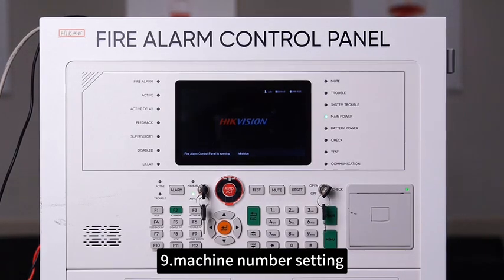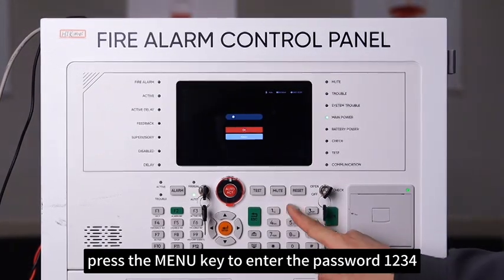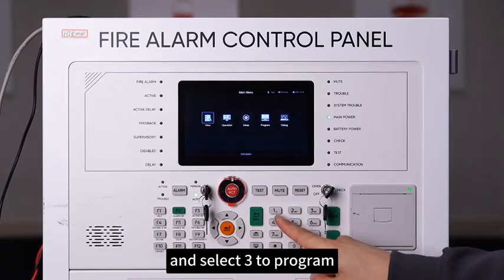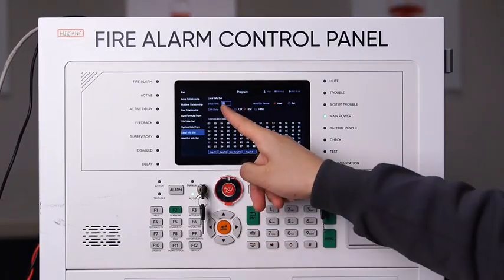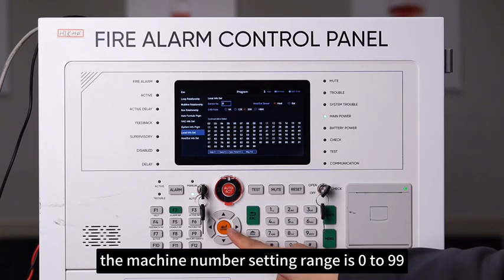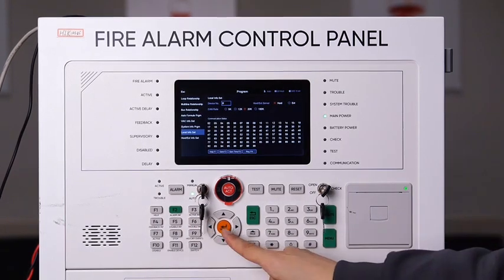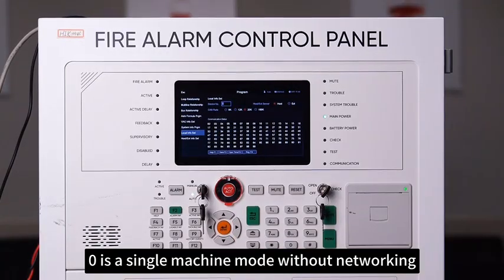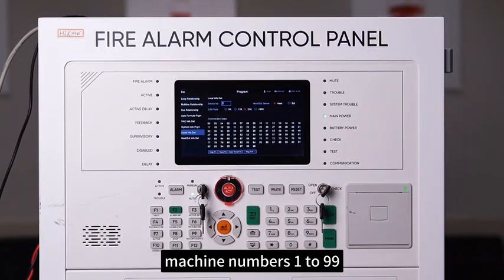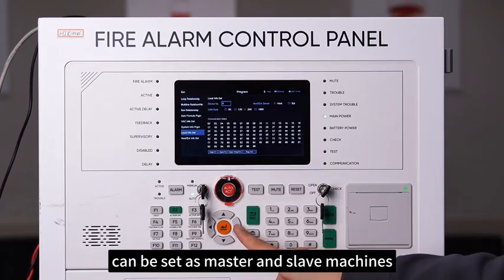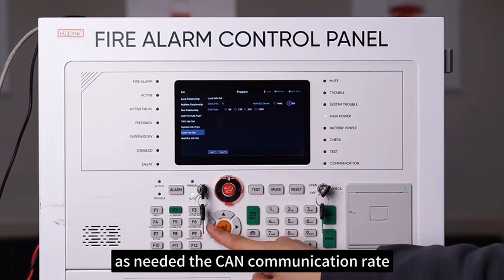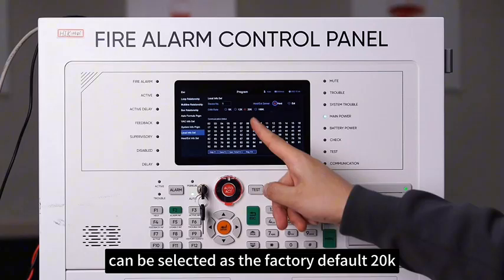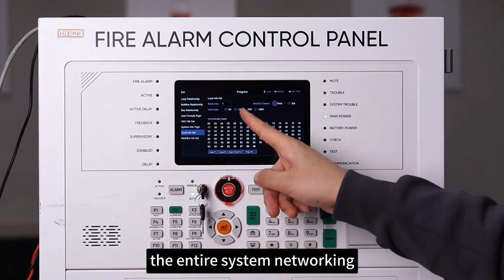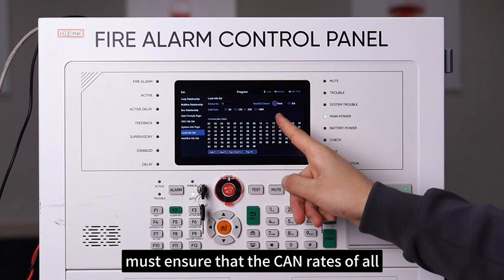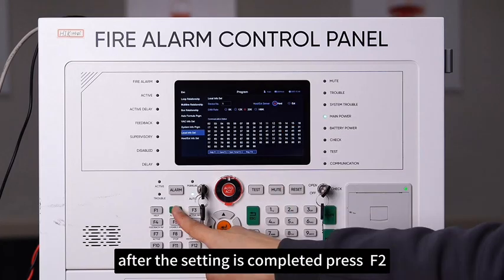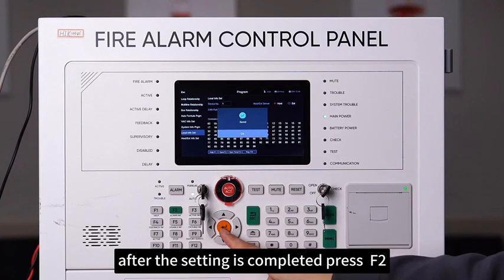9th, machine number setting, press the menu key to enter the password 1234 and select 3 to program the machine information setting. The machine number setting range is 0 to 99. Machine number 0 is a single machine mode without networking. Machine numbers 1 to 99 can be set as master and slave machines as needed. The CAN communication rate can be selected as the factory default 20,000. The entire system networking must ensure that the CAN rates of all controllers are consistent. After the setting is completed, press F2 to save.